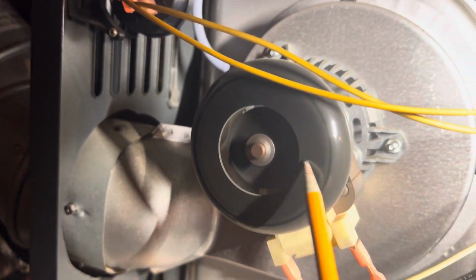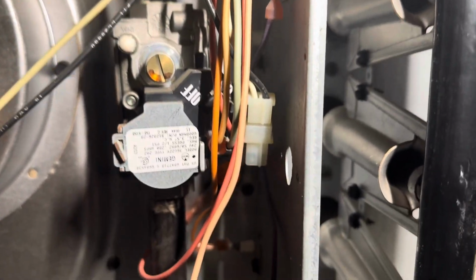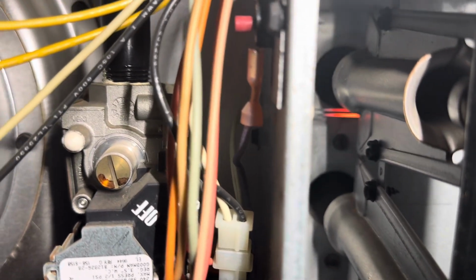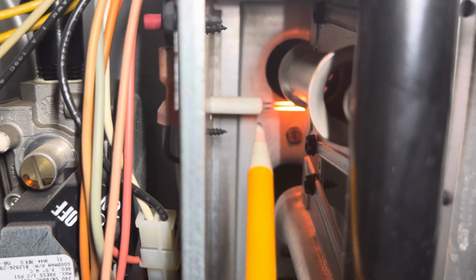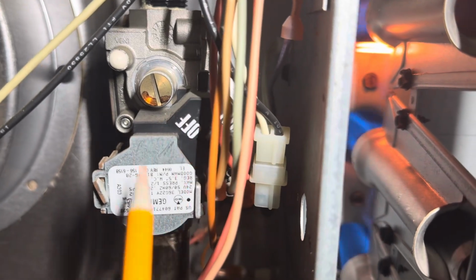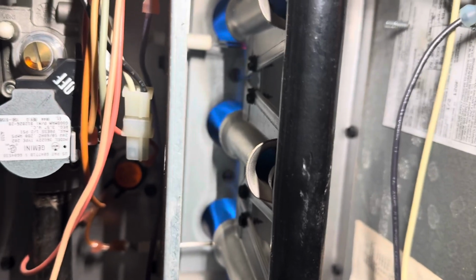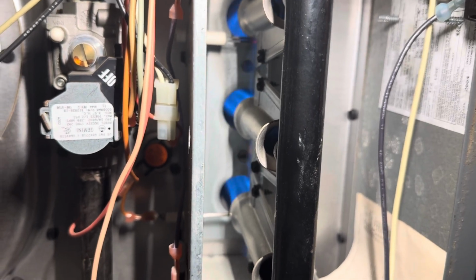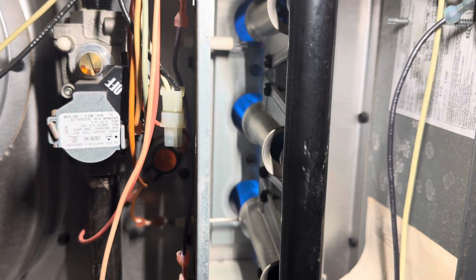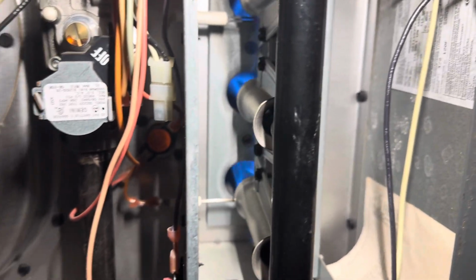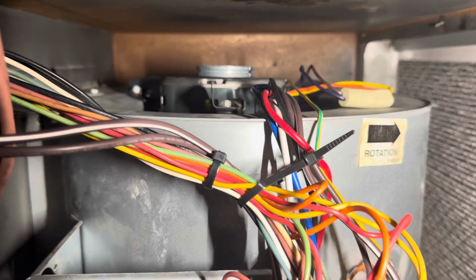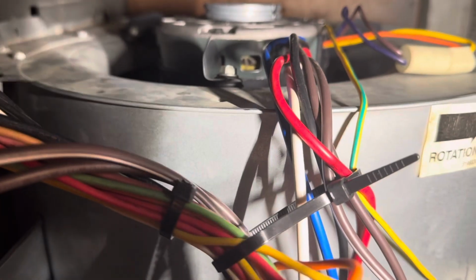Okay, so we saw the inducer motor is on, the pressure switch has closed, and we're now going to watch the cherry red light up here come on, and our gas valve opens, and we have gas. We have burning gas, I should say. So here in a moment, we're going to hear another click, and we will see the blower motor come on. And it just came on.